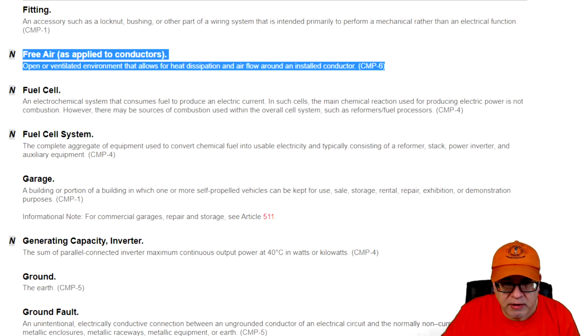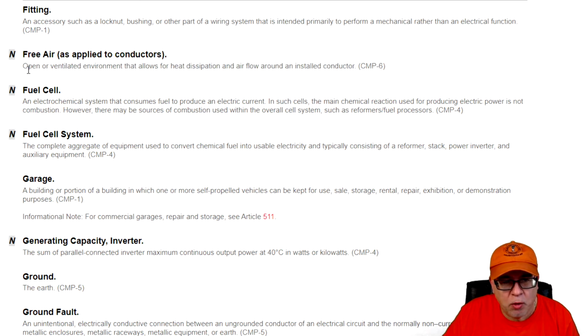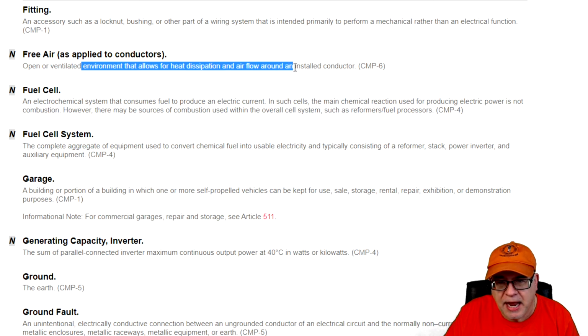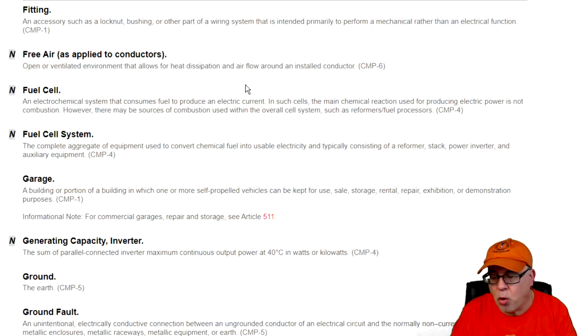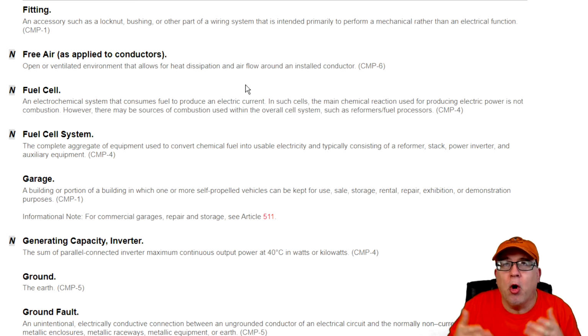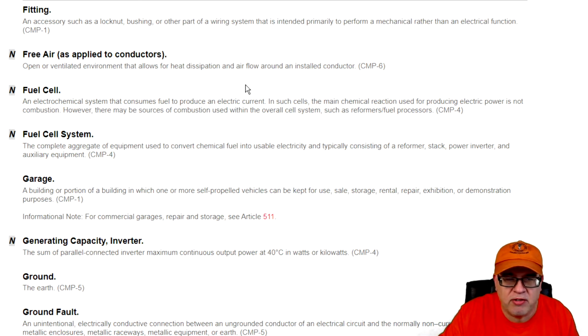All right, so in here it says open or ventilated environment that allows for heat dissipation and airflow around an installed conductor. So again, tray cable, or if they're installed in a cable tray, or when they're all open in the air, like a service drop or on a messenger or whatnot, they're considered open.